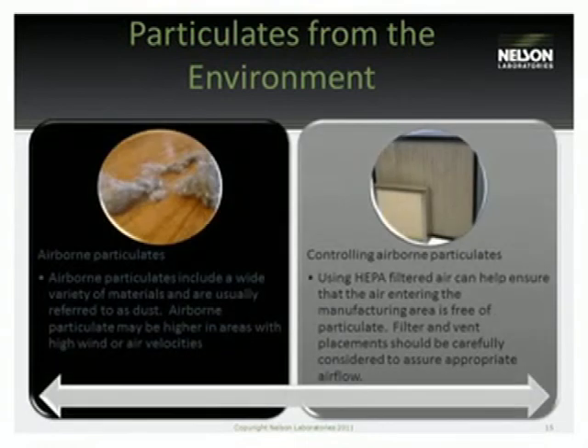Environment can contribute significantly also to particulate matter. We don't manufacture anything here at Nelson, but we do test our clients' samples, and so environment is a big deal to us. Airborne particles are very common, obviously dust, which is probably the most common type of particle that we observe. Using HEPA filtration, as well as reducing the amount of high velocity airflow in the area, are a couple of good ways to minimize the amount of particulate matter that may be subject to the area.